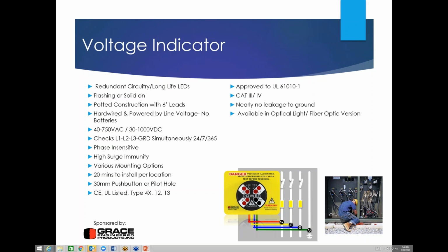So that being said, we'd like the opportunity to introduce the voltage indicator now, which comes in two different varieties of flashing that you see on the screen currently, as well as a solid on. A couple unique things: it's hardwired to the source, and it has a high surge immunity, and you'll see that it's flashing right now. So in a typical system, there is voltage present on L1, L2, and L3, which you see there starting at the 8 o'clock, 10 o'clock, and 2 o'clock position, and no voltage on the ground. If there's a voltage imbalance, the ground would come in and start to flash, or a short circuit somewhere in the system where there is voltage on the ground, it will begin to flash. But if we lose a leg, that would be another opportunity where that ground light would come in and start to flash. In this circumstance, as you see, we lost L1 for some reason. It could be a blown fuse or a tripped circuit breaker, or potentially a lost leg coming in from your power company.